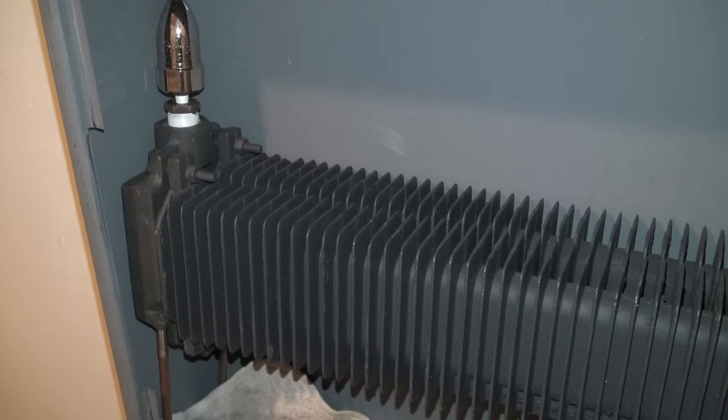Now, a lot of one-pipe steam heating systems have been known to give problems over the years due to pitches being tampered with. In certain cases, a building or a house will settle or shift, and the pitch will completely get thrown out of whack. So in that case, it's not even due to the system not being installed correctly. It's just due to the fact that the building settled or shifted. Now the pitches that were once in there that were supposed to re-pitch and drain everything back to their proper locations is no longer there. So you don't have the option to be able to run it like that.